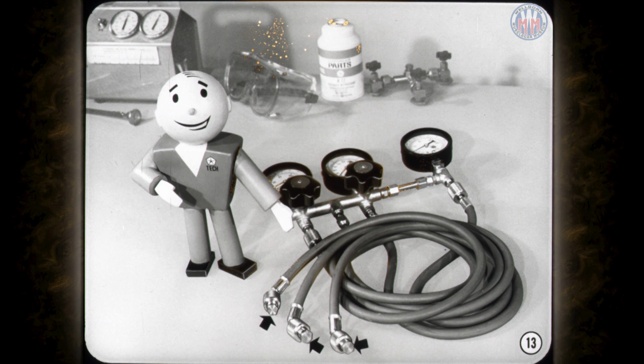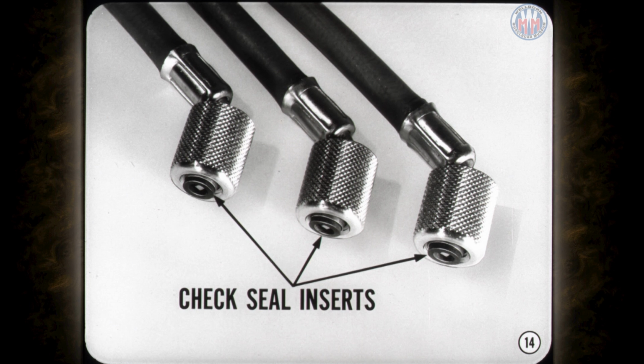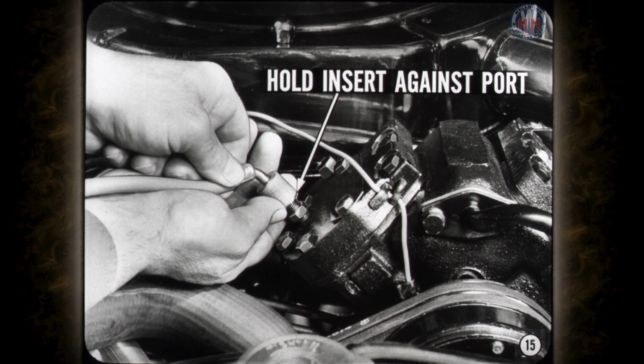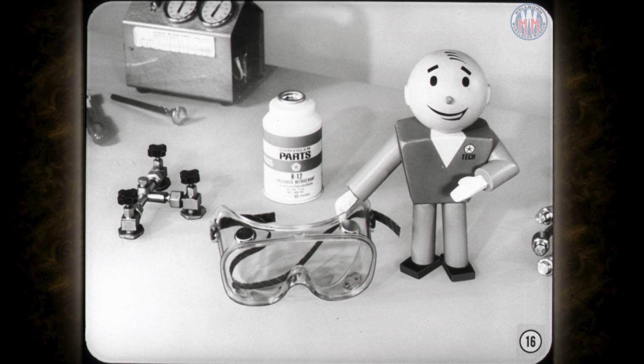When the gauge set is not connected, be sure and plug the hose adapter couplings to keep out dirt and moisture. And make a habit of keeping the valves closed so you won't lose a lot of refrigerant when you connect the hoses. Before you connect the gauge set, give the hoses a quick look to check their condition. Also check the coupling seal inserts because the couplings will leak if the seals are missing or damaged. The valve stem depressors and the hose couplings can release refrigerant as you connect the hoses at the compressor. Simply hold each seal insert tight against its service port while you tighten the coupling, and you can do the job without losing refrigerant. And always remember to be careful when you connect the gauge set or handle refrigerant. Escaping refrigerant freezes on contact, so play it safe by wearing goggles and protecting your hands.